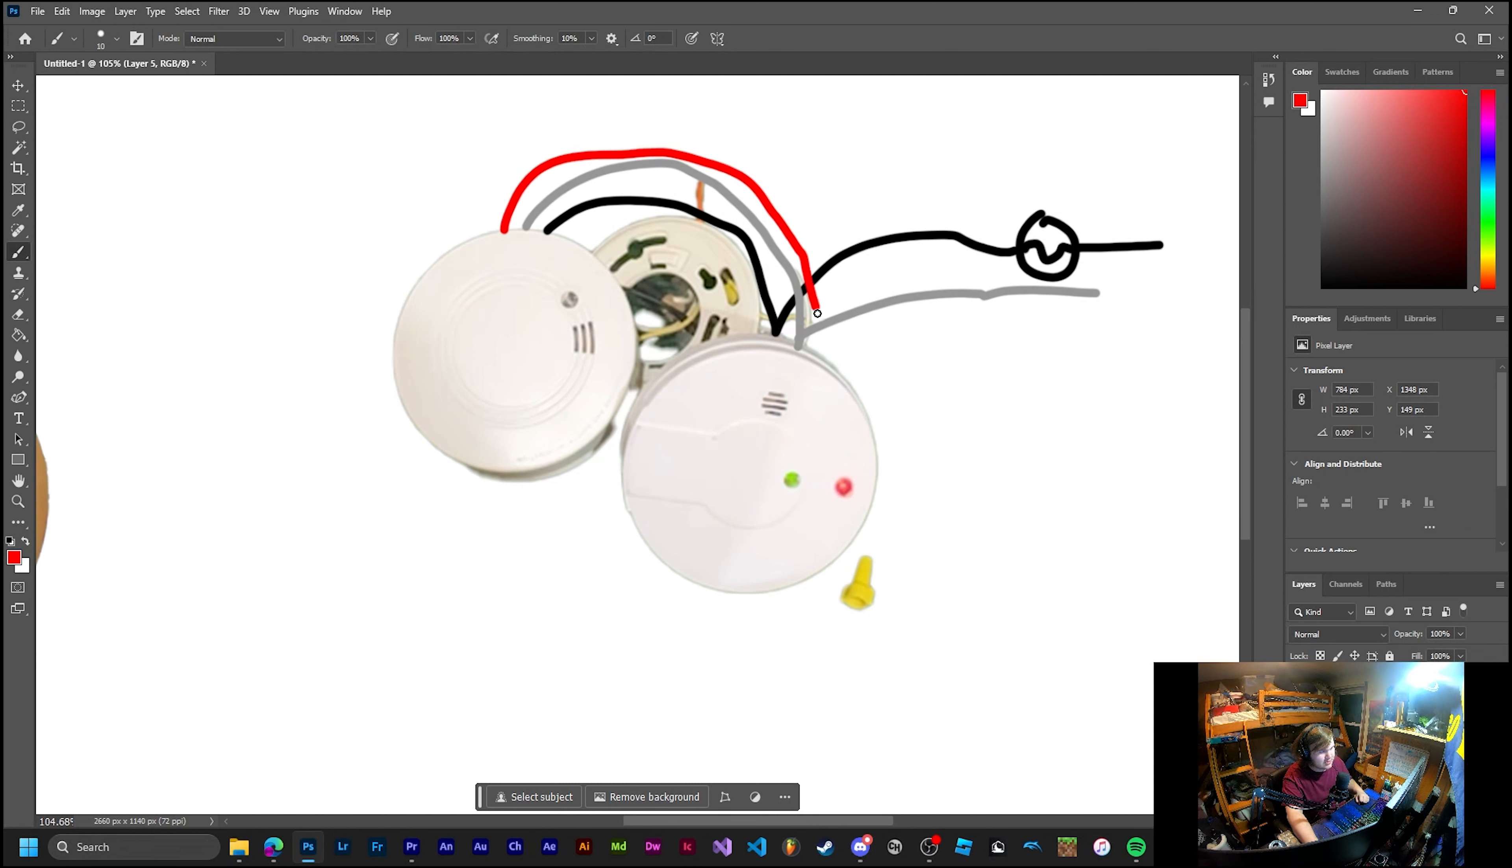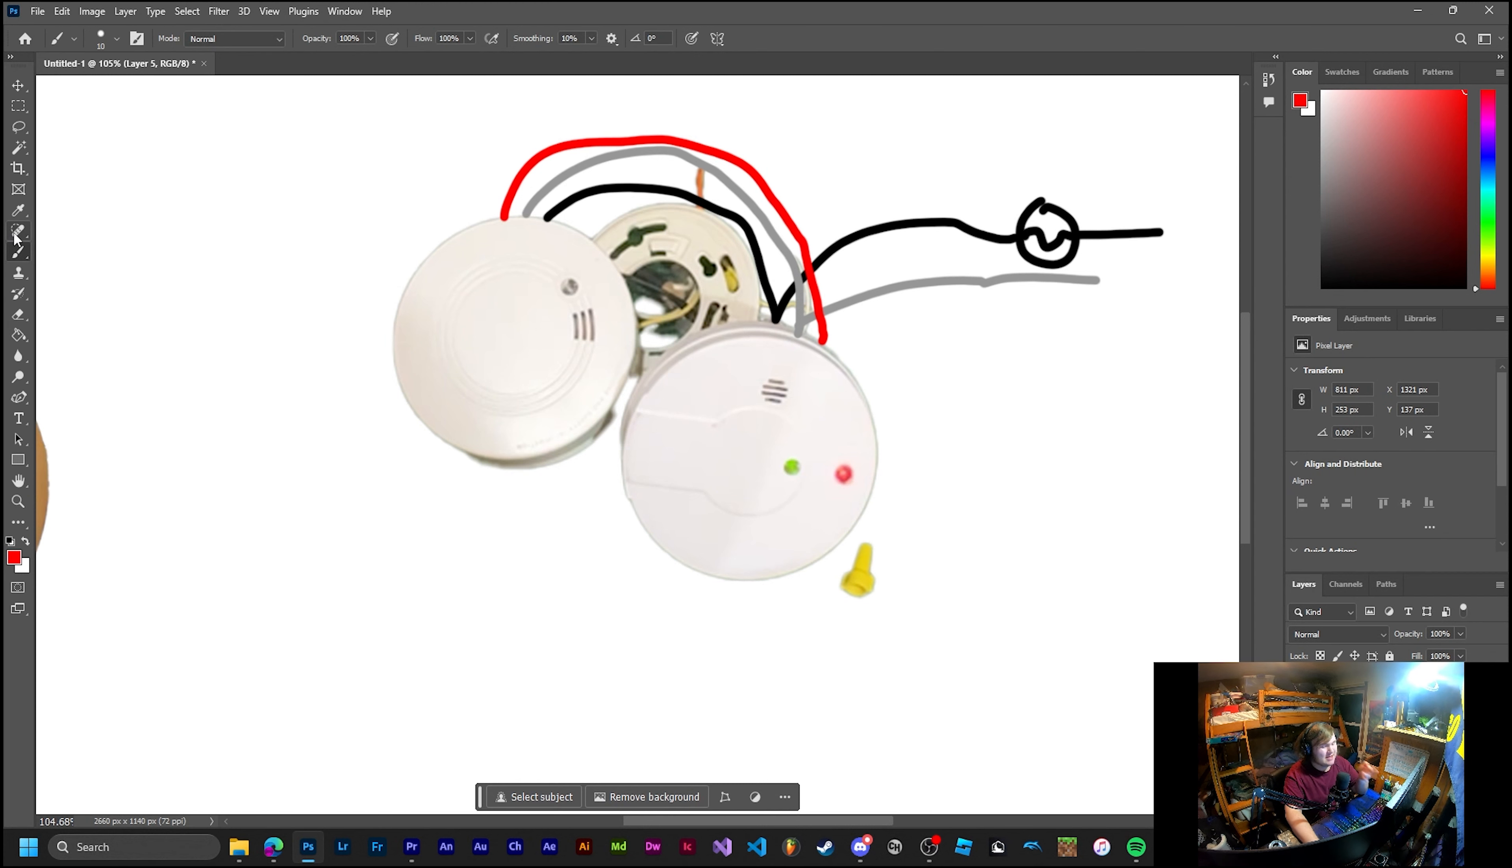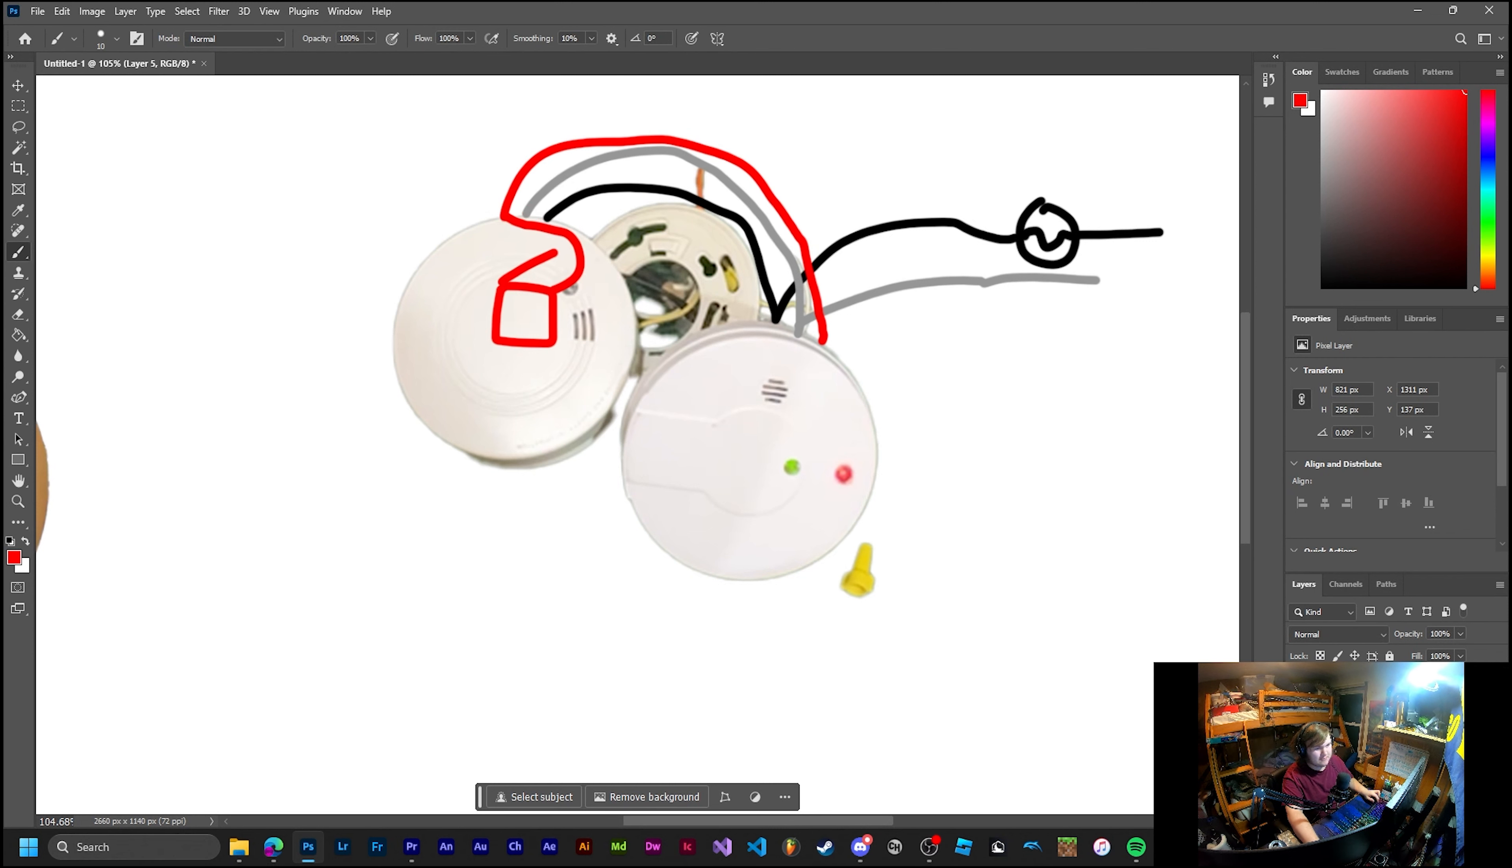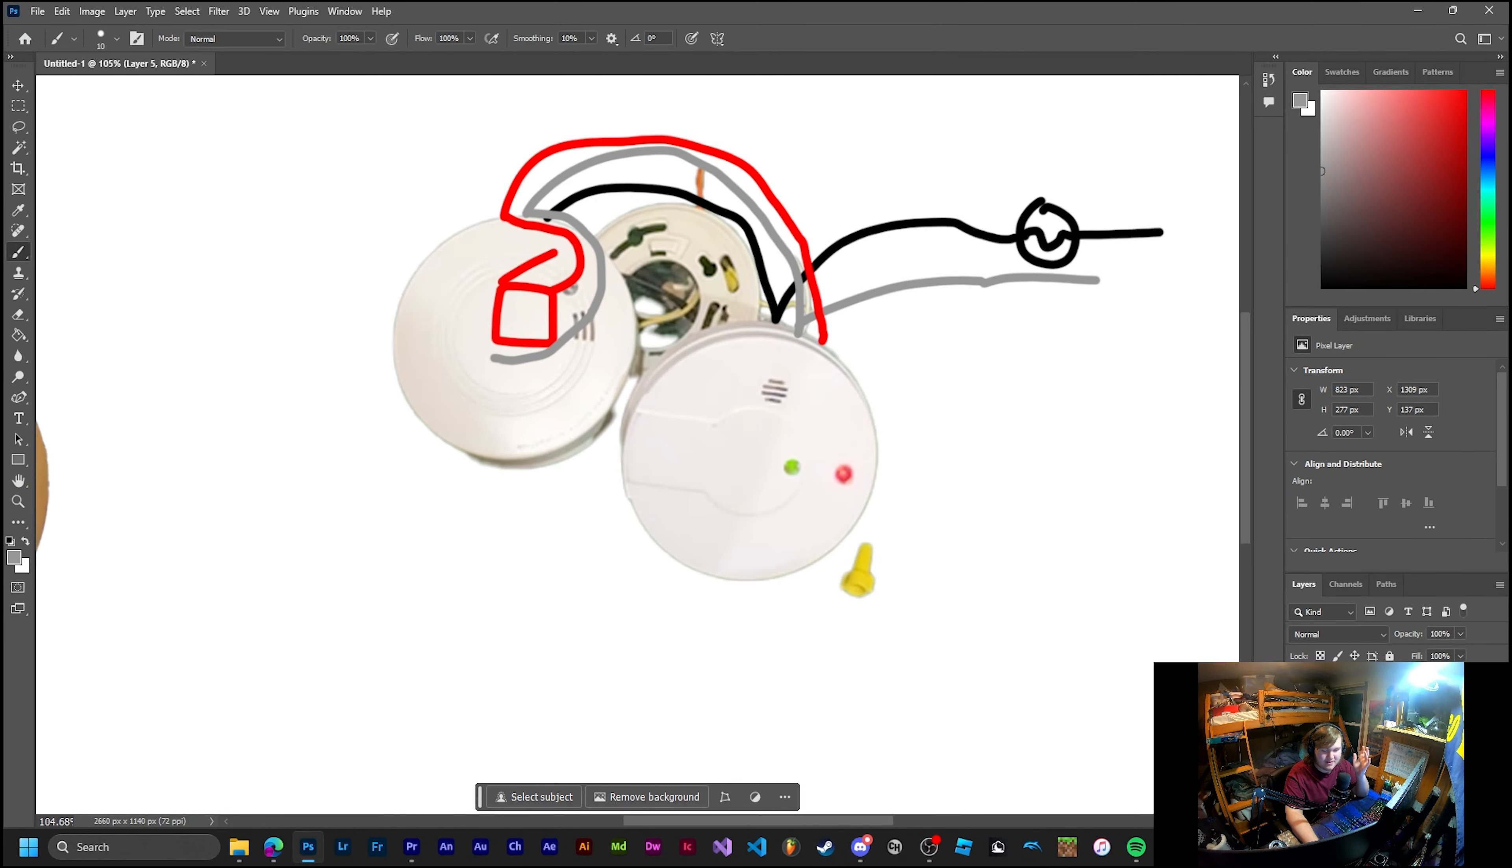That's just our interconnect and that'll go to breaker or whatever you have plugged in. And we have our interconnect which is red. Instead of this being constantly powered, this is actually dead, same for the neutral. But when this alarm sounds, there's a relay inside of it that will click, that will make contact with the red. And since the gray is our neutral, that is our negative. So if you press the test button, it's going to send power down this red line which will activate the other alarm.